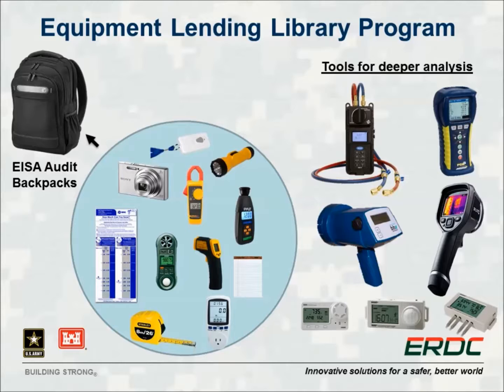Looking at some of these here, right up here we've got a ballast checker. One of the most common types of lighting in our federal buildings are tube fluorescents, and you see them all over the place. They're a relatively efficient way to do lighting in general. But we can test whether they have electronic or magnetic ballasts, which tells us whether they're candidates for direct replacement with LED, without having to redo any wiring. So that can give you useful information.